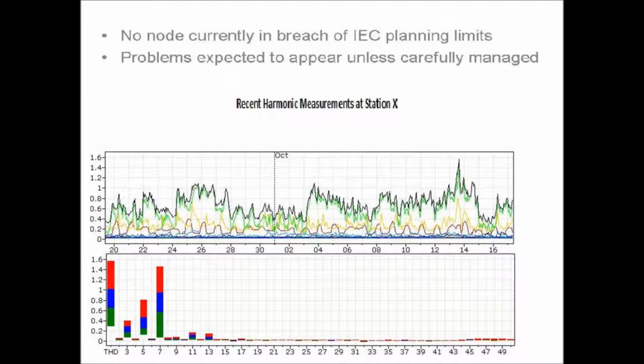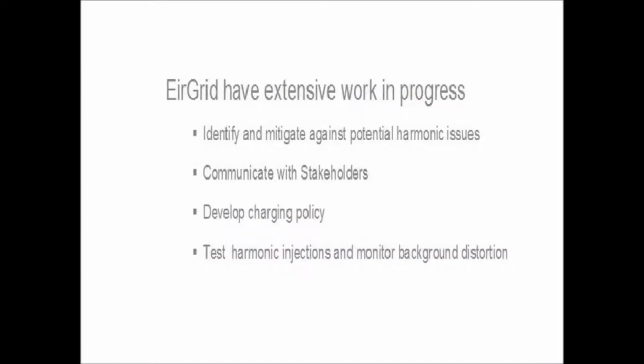But the problem area is the 7th harmonic. If you look at that, you see that the 50 to 95% are around the 1 mark. That's fine, but you've got to remember that at the 7th, we're only allowed to go to 2. So we're halfway there already at this station for the 95th percentile, and then for the 95 to 100, say you're in an outage or something is going on, you could end up in that situation, and very quickly you find yourself up around the 1.4, 1.5 mark, which is getting closer and closer to that limit. So that's where we are today. The system is okay, but we have to keep an eye on it, I suppose is the message.